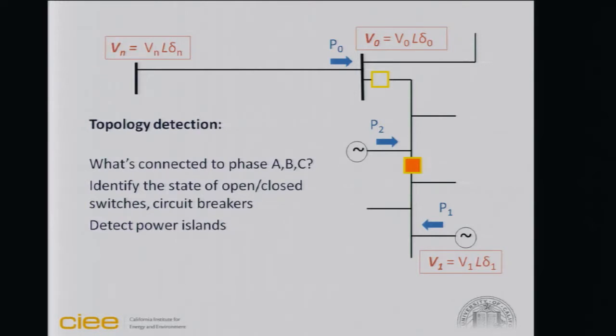A safety-relevant observation is detecting if there's a power island. You can certainly detect that by measuring the phasor on either side of that open switch, that open breaker.